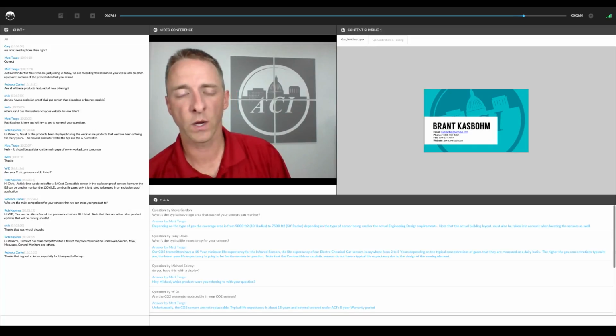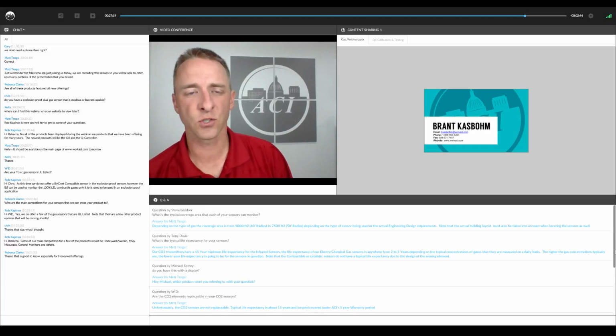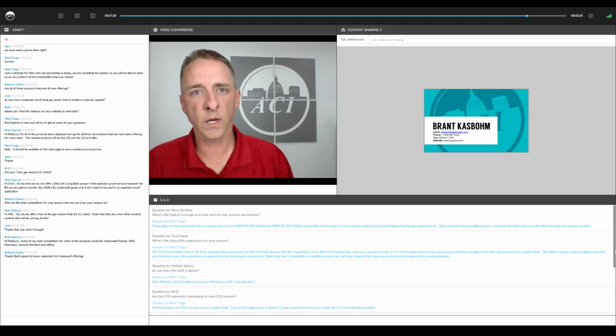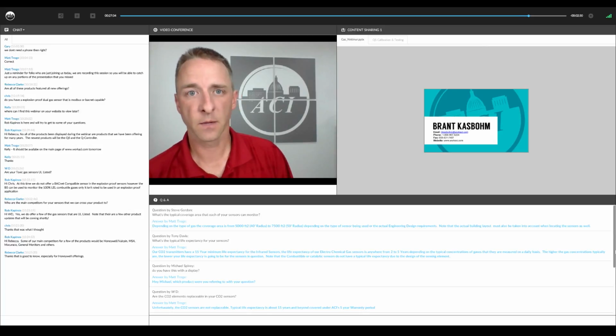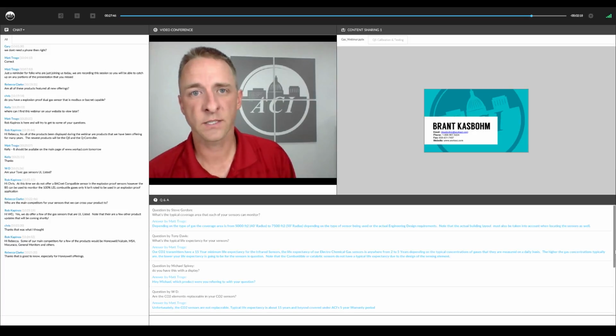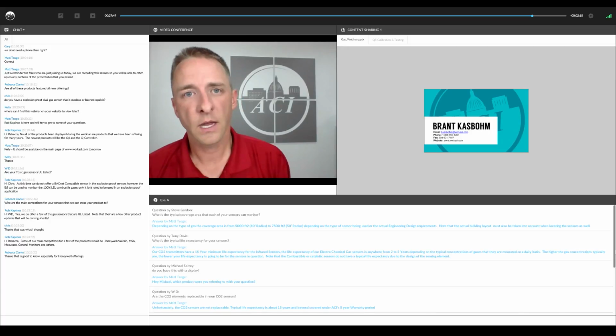So as it stands now, VOC sensors tell us something's present in the air. It doesn't tell you how much or even what it is. So right now we feel it's more effective to monitor a specific gas and a specific level of that gas than a broad VOC sensor. There's rumors that ASHRAE might put out a recommendation regarding VOC sensors, or set a standard or a guideline for that. And if and when that happens, you can bet that we'll have a solution for that. But as of now, we just aren't sure what the usefulness or the benefit of VOC sensors are.